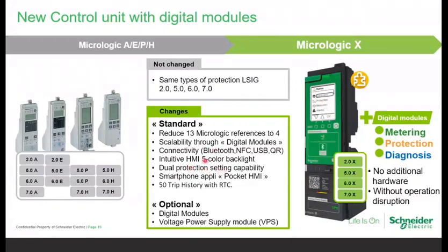Then again, a very important point is that the MTZ ACB, be it any release, I'm repeating, comes with dual protection settings by default. You don't need to pay anything extra for this dual protection setting. Why is it important? You all know, if you have two sources, first is the electricity board, second is DG, whenever a switchover happens, we have a single protection setting installed in our breaker. So whenever a switchover happens between the electricity board and the DG, our settings are the same as the electricity board. It means there is scope to further enhance the safety parameter of the breaker. So here we can set two protection settings. One will be for the electricity board, second will be for the DG. Whenever a switchover is happening, by default your breaker will select the corresponding protection settings. So this will give you enhanced protection, enhanced safety.